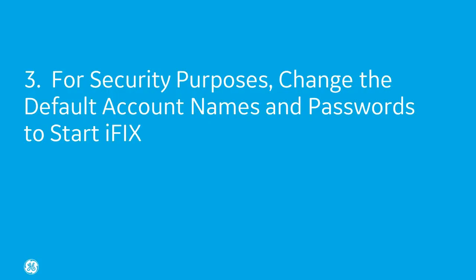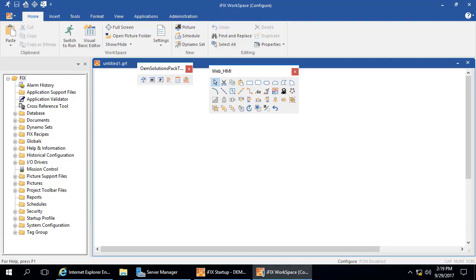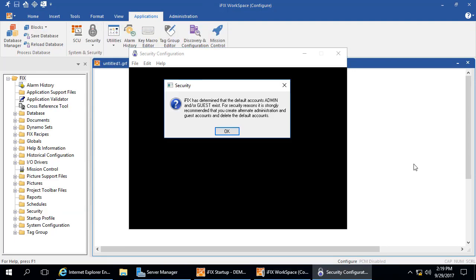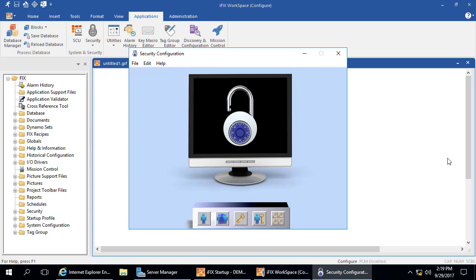For step three, for security purposes, it's really important that you go in and change those default usernames and passwords. In the iFIX workspace, on the Applications tab, click Security, and then Security Configuration Utility. Click OK, as this is what we're going to fix. Next, click the Users button.